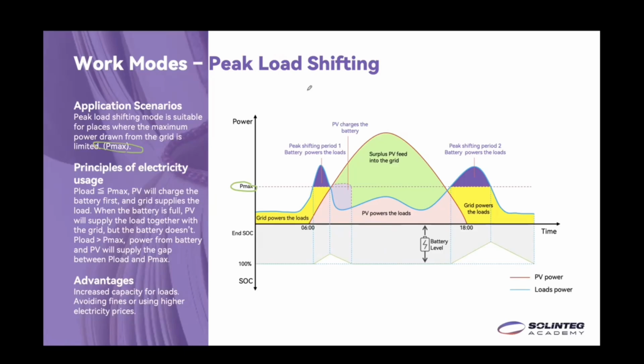So we can divide this working mode into 2 conditions. The first, when the power required from the load is lower than or equal to the Pmax. At this stage, the PV and the grid will support the home load together and also charge the battery. During this stage, the battery won't discharge. Only when the power required from the load is higher than the Pmax will the battery discharge and fill in this gap.